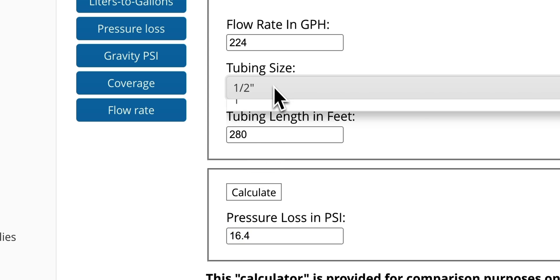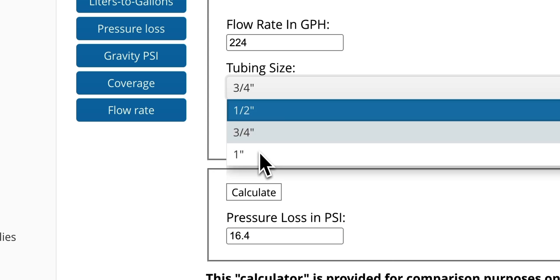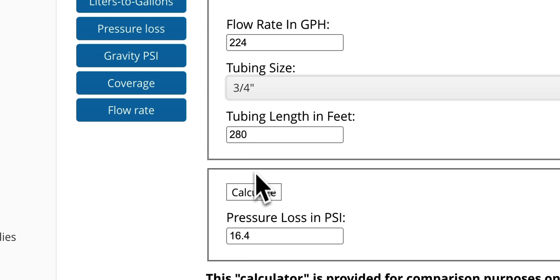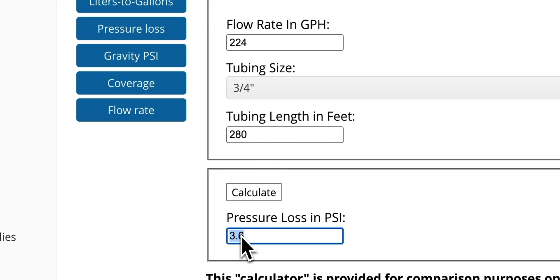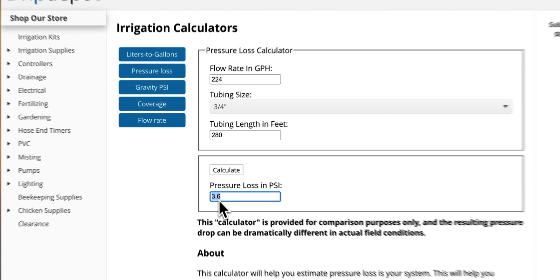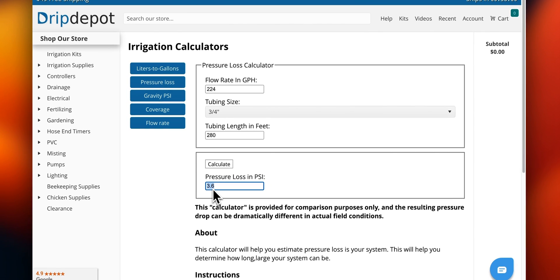Bumping that up, 224 gallons per hour going through 280 feet of three quarter inch mainline would only lose 3.6 psi from friction — a fairly minimal amount.